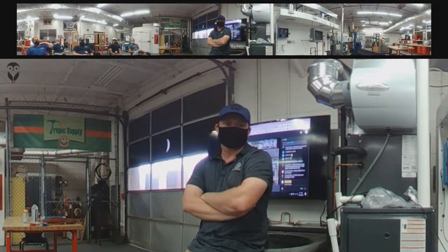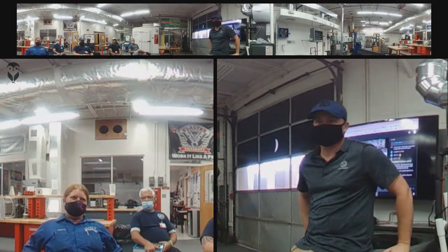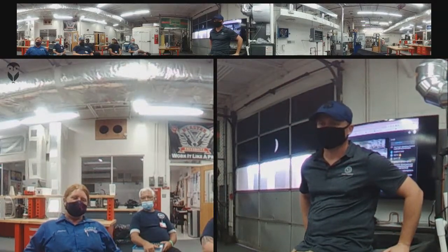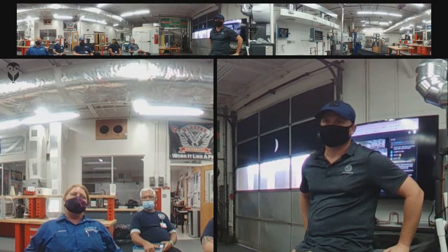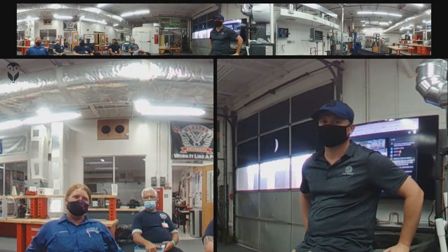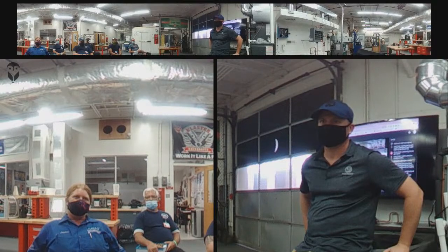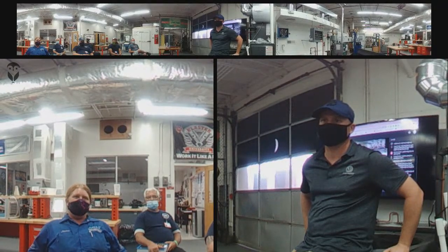I was at a first-year maintenance on a new system and found oil on the cork tape on the liquid line. Okay. I bubble tested and found a small leak. I was able to locate it. Nice. And this was on the inside or the outside? Inside.